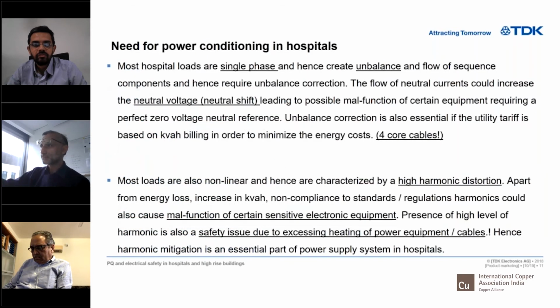Now, as I said, most of them are single phase loads. That means they have an unbalance. They create sequence components flowing all over the system. And then you create a neutral voltage shift. That means some of the equipment which is connected line to neutral and requires zero voltage on the neutral can even start malfunctioning. I won't get into the details. If somebody is interested, I can give you examples.